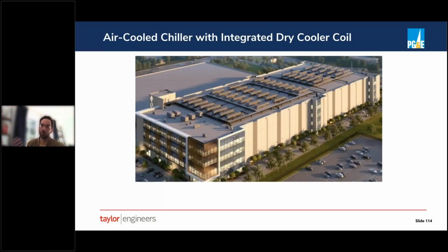So a dry cooler is less efficient than a traditional waterside economizer, because what you're approaching is different. With a traditional waterside economizer, we're able to approach the ambient wet bulb. With a dry cooler, we're approaching the ambient dry bulb. But obviously in the middle of the winter, there's still going to be a lot of hours in most climates where that ambient dry bulb is plenty low to do effective cooling without needing to use refrigeration.